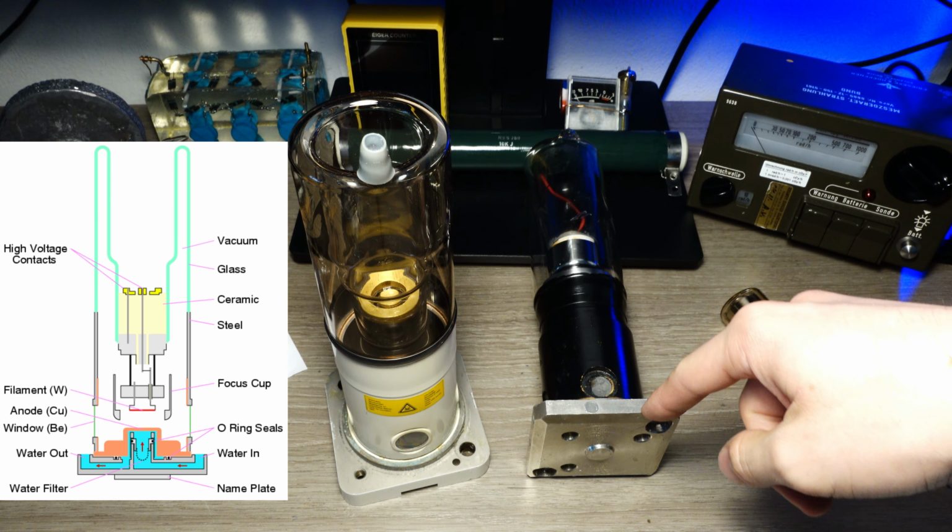And so you have these 4 windows to capture the X-rays coming from the X-ray beam parallel to the filament or perpendicular to it. Why? Because the X-ray coming from this window would have a lower diameter, because the focal spot of the filament is lower. As you can see, it's only the diameter of the filament, while the X-rays coming from this window will have a much bigger focal spot due to the entire length of the filament emitting the X-rays.